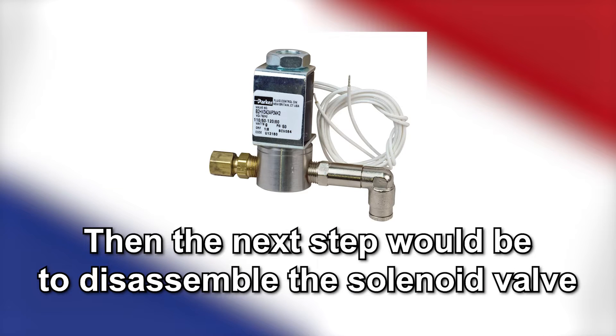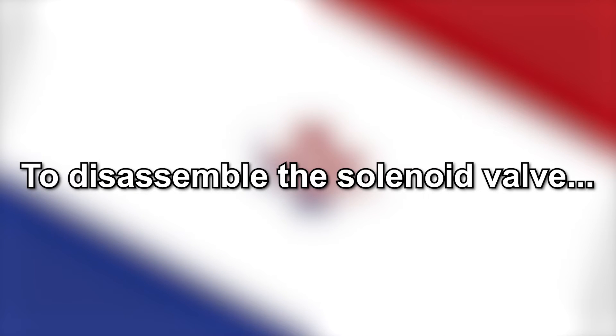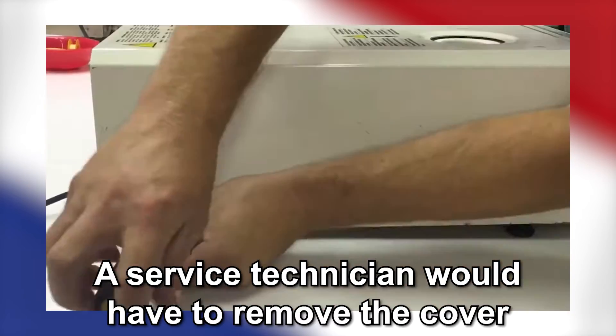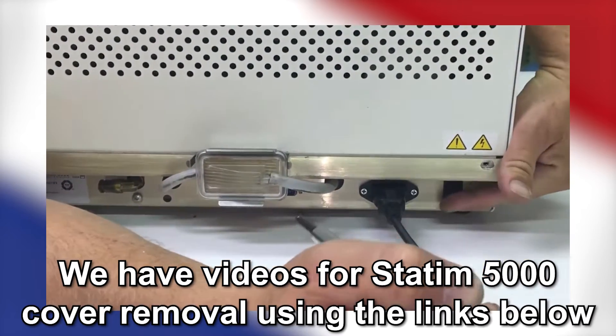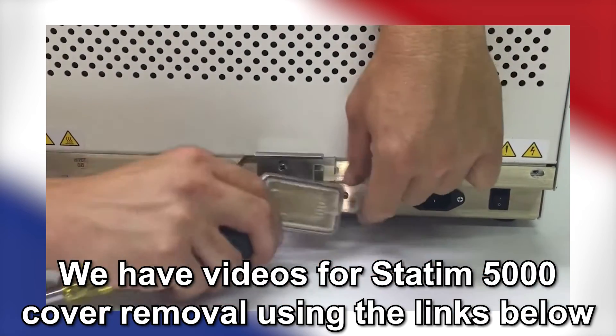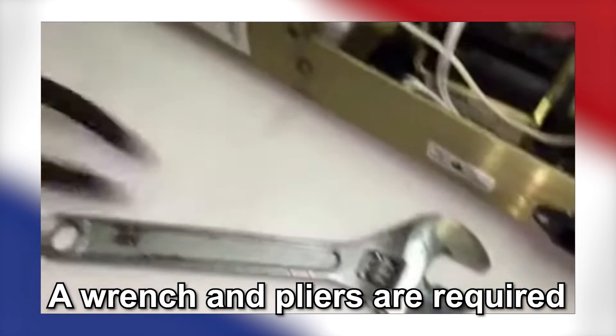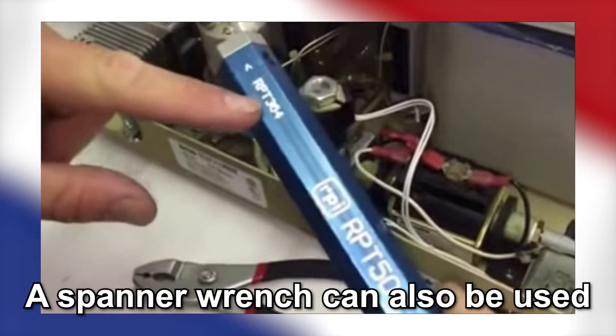If there are no visible leaks, then the next step would be to disassemble the solenoid valve and check for debris or the plunger sticking in the plunger tube. To disassemble the solenoid valve, a service technician would have to remove the top cover of the Statim 5000 to reach the solenoid valve. We have videos available on our YouTube channel using the links in the description on removing the top cover of the Statim 5000. If a service technician removes the solenoid valve, a wrench and pliers are required to properly remove it.